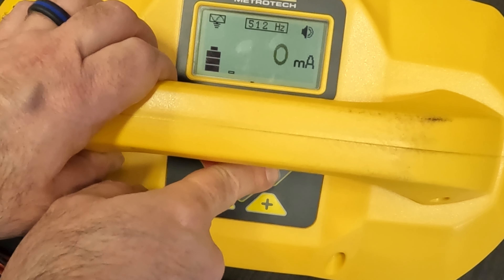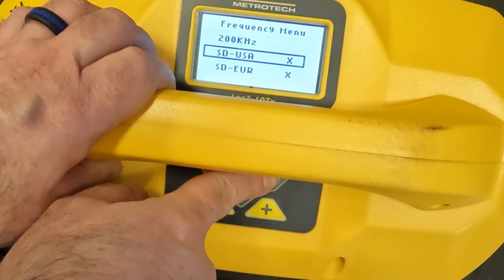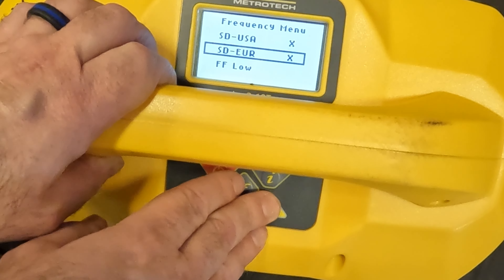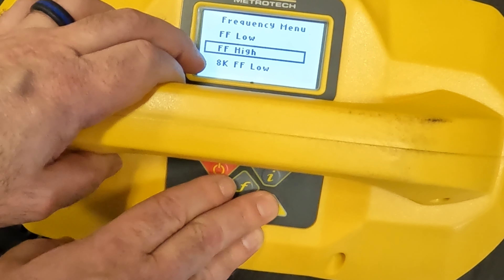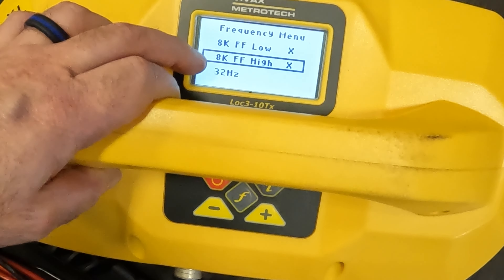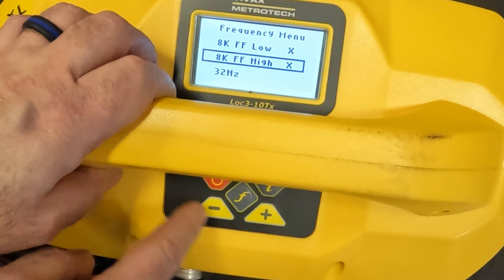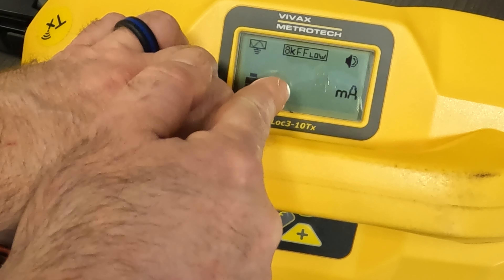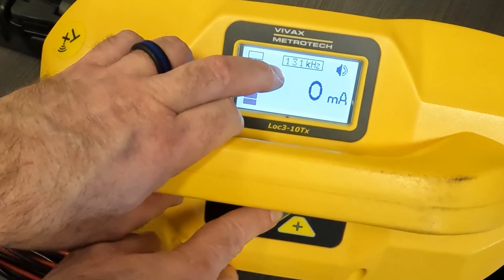So again, I'm going to push my I button seven times. Now I'm into my menu screen here. I'm going to go ahead and scroll down. Again, I've got my FF low and FF high, but I want to make sure that my 8KFF low and high are turned on. So I just push the F button once I'm next to those and that will select them. I push my I button to get back to the main screen and now I'm in 8KFF low. If I push the frequency button, I will also be able to scroll through to 8KFF high.